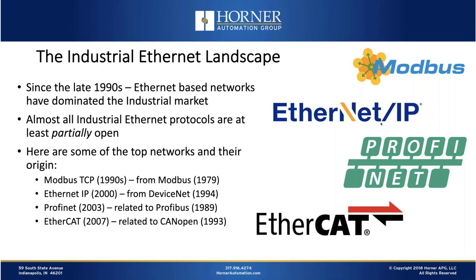Today there are multiple industrial Ethernet protocols, and most of them are at least partially open. Keep in mind that 25 years ago, most protocols were proprietary — things have definitely changed. Today the most commonly found networks include Modbus TCP, which had its origins in the Modbus serial protocol from the late 70s, and Ethernet IP, which is what we're going to talk about today. It had its origins with DeviceNet, a protocol that operated over CAN, still around but faded considerably since the 90s.